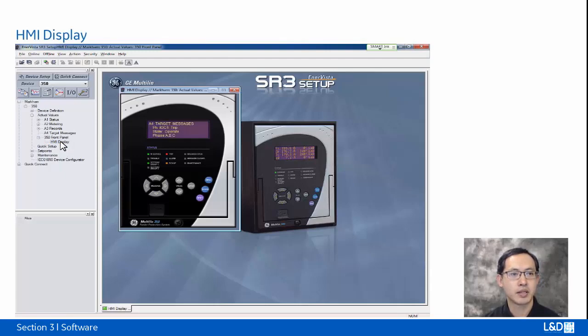And now we can see exactly the same display as I have on the relay front panel. So now I got one fault current injected to the relay, and I can see the relay operated in the front panel. If I press the reset button, the message won't go away because the fault is still applied. So if I clear the fault and now press the reset button from the HMI display with the software instead of the front panel, I can see that the message has disappeared.